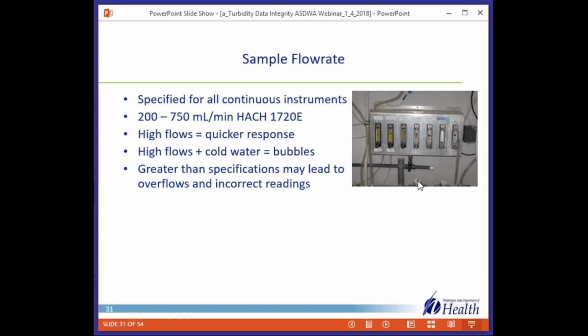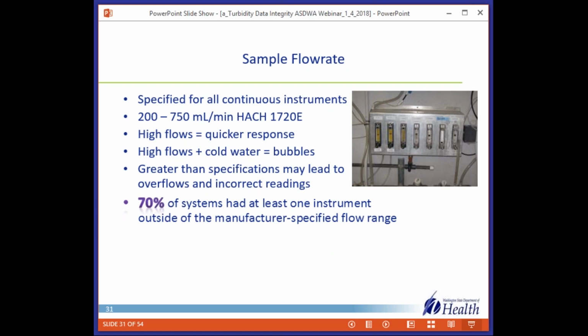So sample flow rate is specified for all continuous instruments. 200 to 750 mils per minute for the 1720E. High flows give you a quicker response, and high flows plus cold water could get you bubbles, so that might be an issue. Greater than specifications may lead to overflows and incorrect readings. What did we find? 70% of the systems had at least one instrument outside of the manufacturer's specified flow range. Now, most operators know there is a specified range. A few don't know what the range is, but they know it. We found a wide variation in measured flows, both above and below the value.